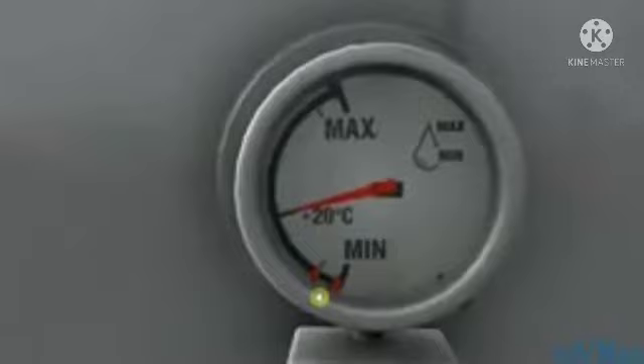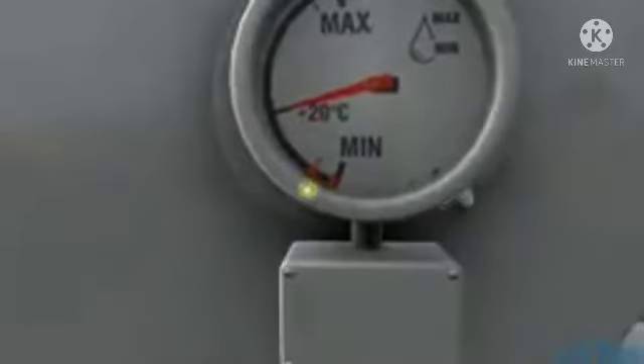If we look also on the bottom, we can see these 2 red lines or 2 red triangles. These are used as low level and low level alarm set points. It's important that we maintain a good head of insulating liquid within the conservator tank, because if that level drops down, we could get a catastrophic failure of the transformer, and obviously this is not what we want.